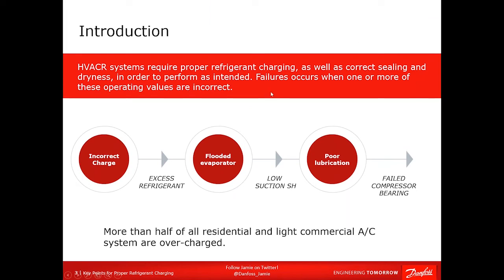HVAC systems require refrigerant as their lifeblood — it is the refrigerant that absorbs and rejects heat by changing state. When you have the correct amount of refrigerant, it is boiling at the correct pressure and temperature, and you are running out of liquid or vapor at the correct point towards the outlet of the coil. So you have proper superheat and subcooling, and you're not operating at too high or too low a temperature, which reduces efficiency.